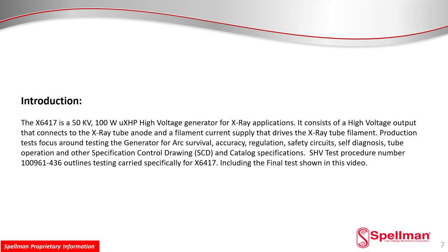As a brief introduction, the X6417 is a 50 kilovolt, 100-watt micro-X-HP generator for X-ray applications. It consists of a high-voltage output that connects to the X-ray tube anode and a filament current supply that drives the X-ray tube filament. Production tests focus on testing the generator for arc survival, accuracy, regulation, safety circuits, self-diagnosis, tube operation, and other specifications.